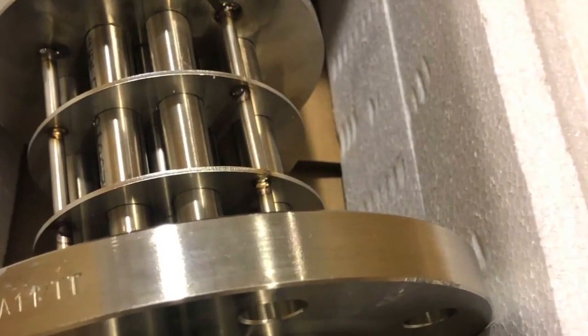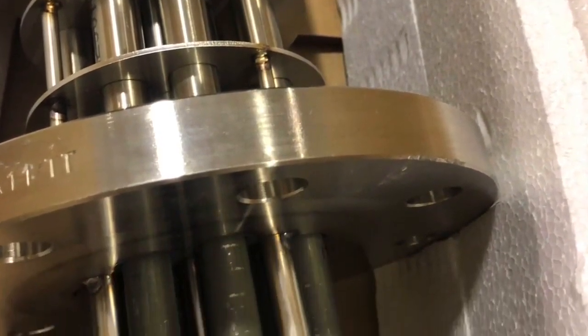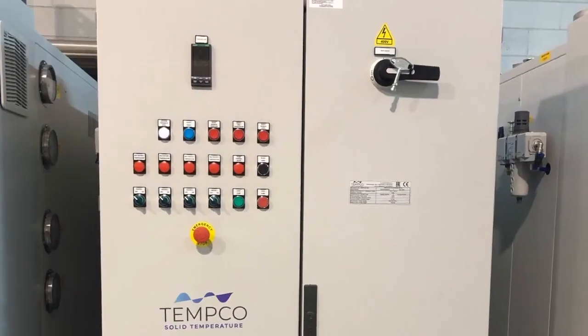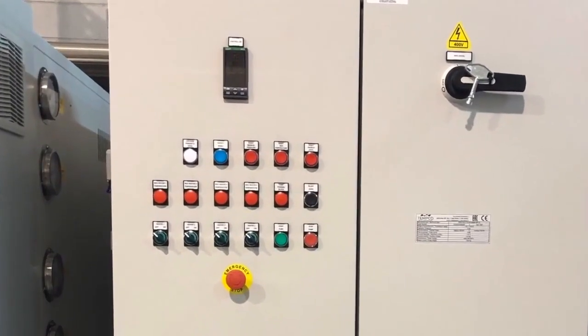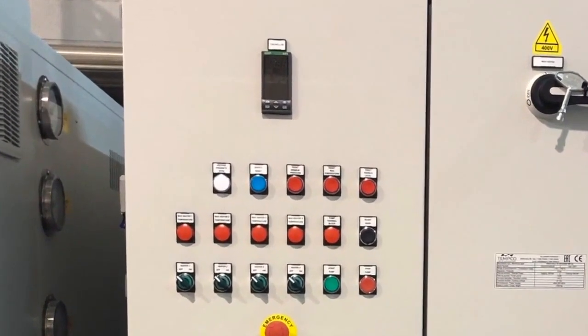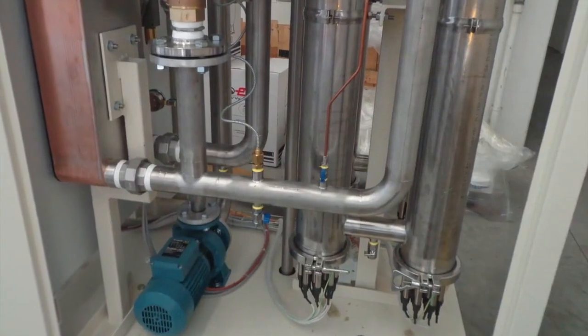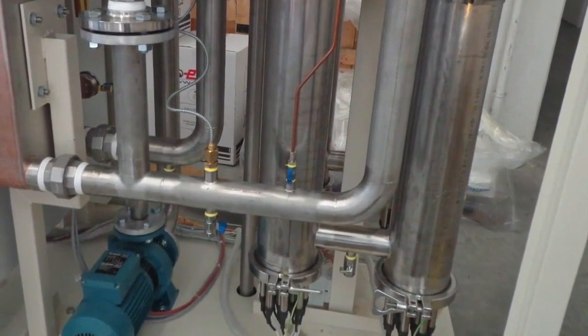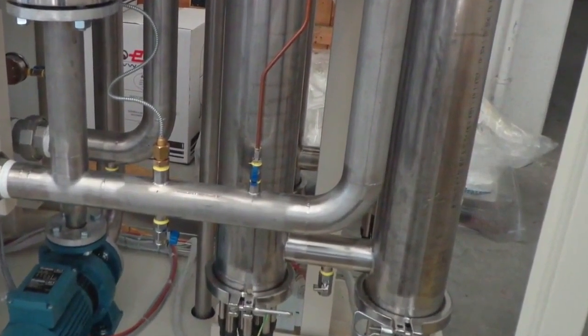Regarding electric heating, the situation is somewhat distinct. In practical terms, it involves adjusting the power of the heating resistors. How do we do it? We do it through modulating static SCR relays. In this case, by using a PID temperature control system, which operates with a modulating proportional band control, we can request the resistors to provide the actual power needed at that moment to reach the set point or to maintain the temperature of an industrial process.